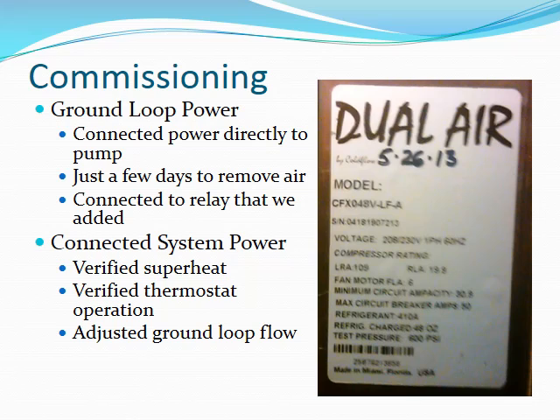After the electrical was ready to hook up, we commissioned the system. I first started the ground loop power. I directly connected the power to a 110 circuit for a few days to remove any kind of air, and then I connected that power to a relay that we had added to the system. After that, we connected the system power. My friend, who was the HVAC person, verified the superheat, verified the thermostat operation, and adjusted the ground loop flow so that it was working at a 10-degree differential, which was what was recommended by Ingram Water and Air.